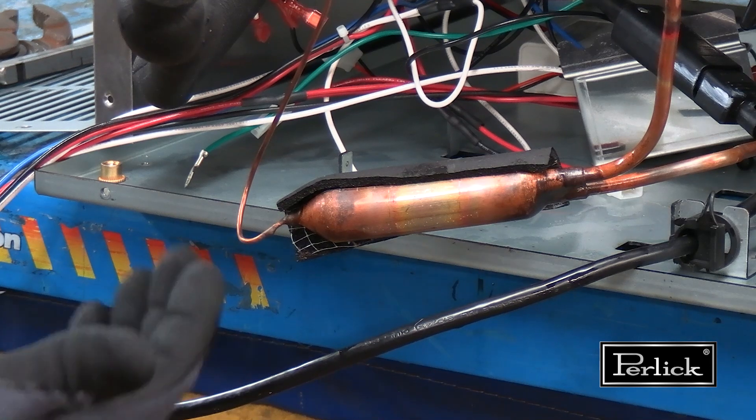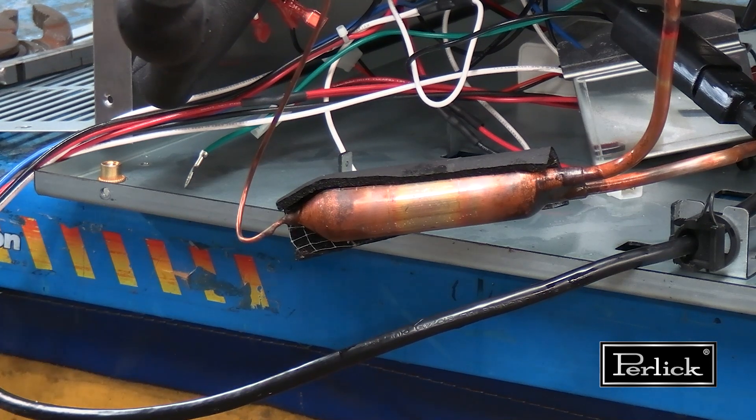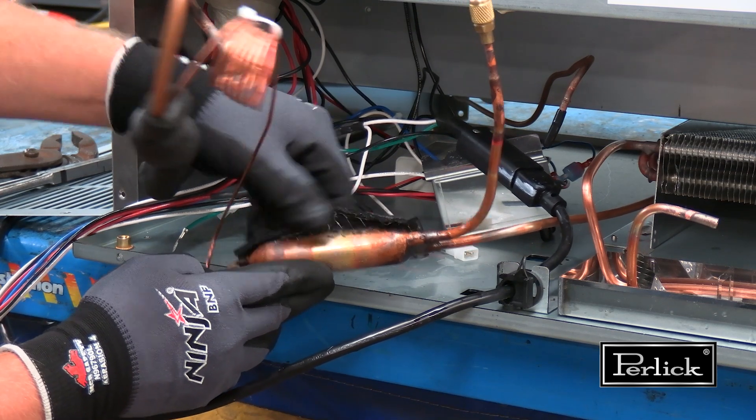Any time the sealed system has been open to the atmosphere, it is strongly recommended that you change out the filter dryer on the unit. To remove the dryer, the first step is to remove the Armaflex tape from the body of the dryer.